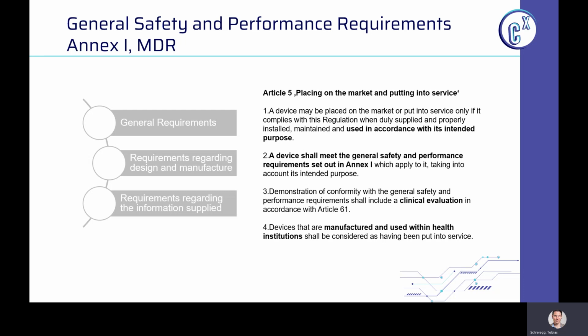A clinical evaluation is compulsory under Article 61. However, the extent of the clinical evaluation might depend on the maturity of the technology applied for the medical device in question and does not necessarily need to encompass a clinical investigation, a study, in every case. Health institutions can also manufacture medical devices on their own. This is a very important part, but it doesn't exclude them from being mandated to follow the medical devices regulation. They need to follow the MDR, but of course CE marking is only needed if the product is being placed onto the market, that is, if it is being transferred into another legal entity, for example.